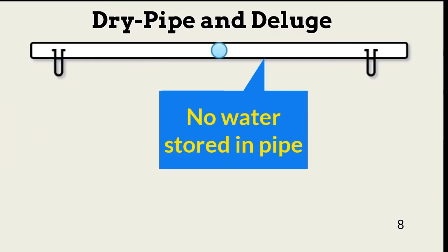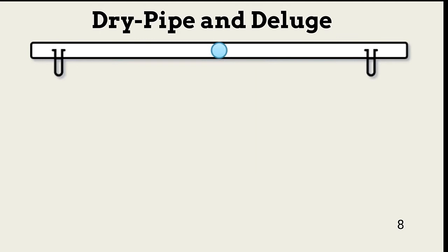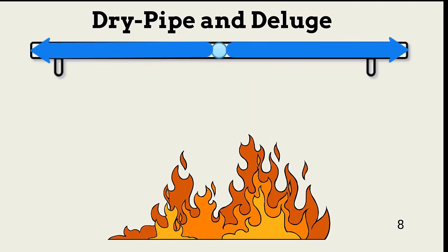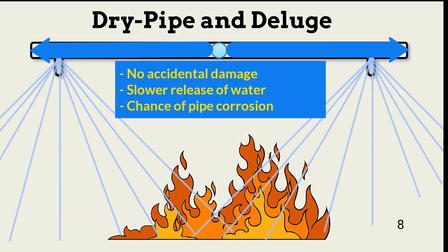Dry pipe systems are similar to wet pipe in design and the delivery of water to fire locations. The primary difference is the lack of water in the pipes feeding the valves until a fire is detected with heat, smoke, or a manual alarm. The advantage is the lack of accidental water release due to condensation or valve failure. The disadvantages include increased time to water release onto the fire, and empty pipes might have an increased chance of corrosion.